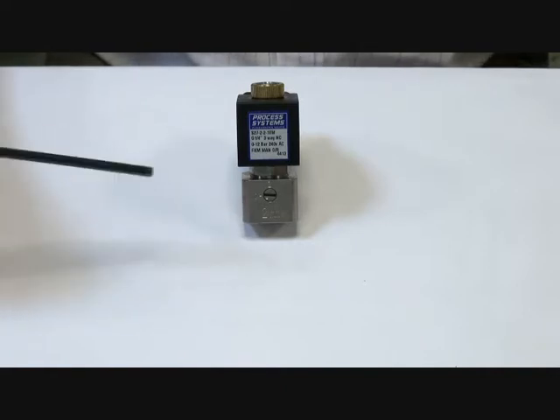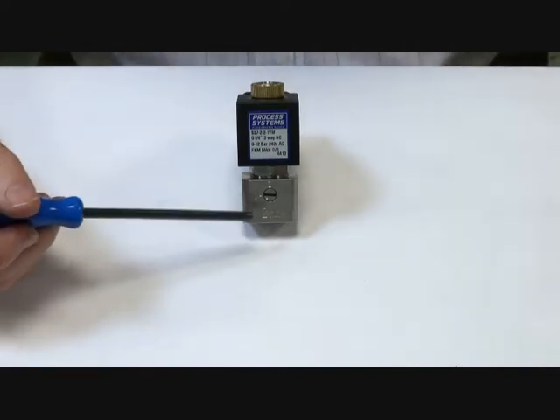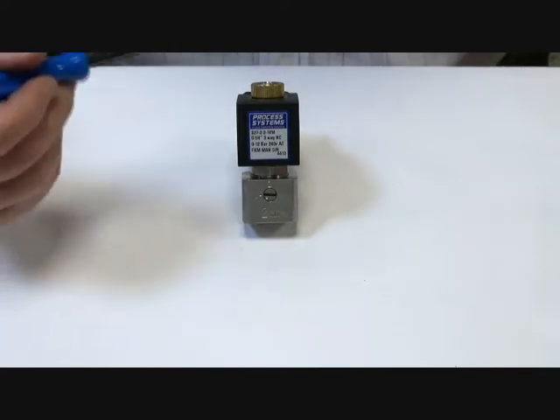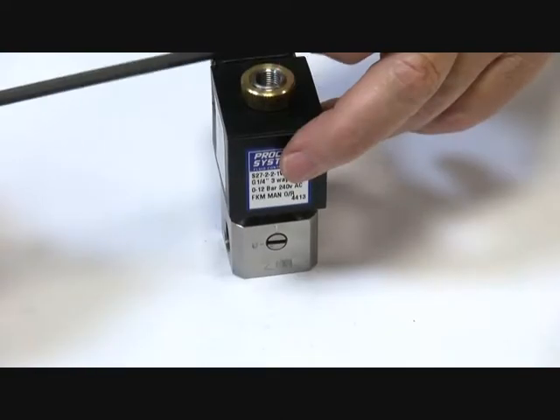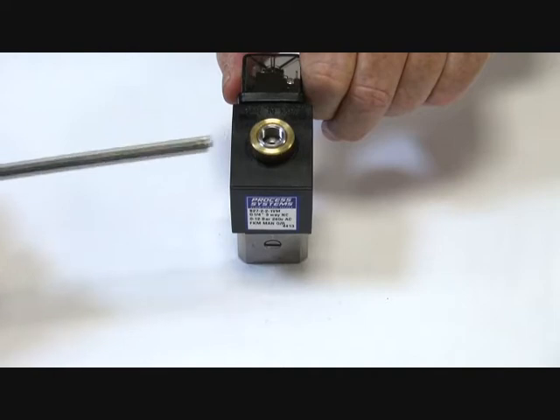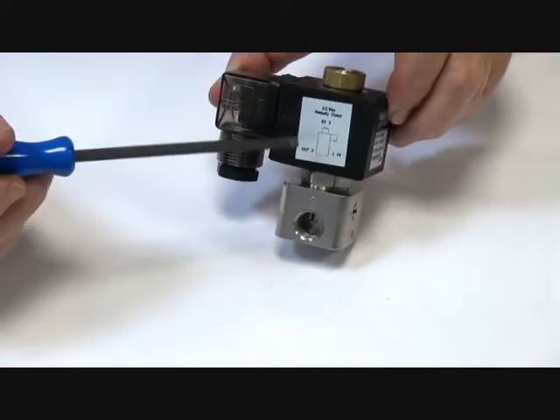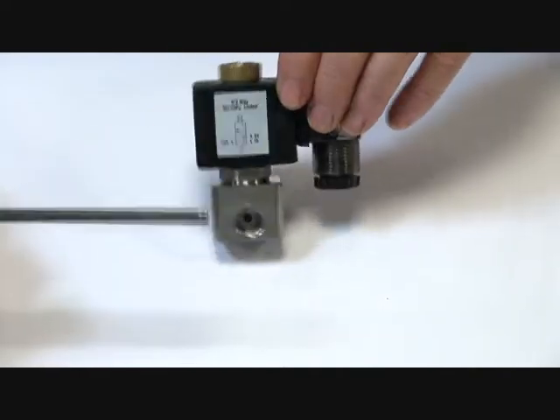It has a 304 stainless steel body, quarter inch BSP threaded. The supply goes into port 1, out port 2, exhaust at the top through port 3. There's a diagram on the side of the valve showing how to pipe this up.